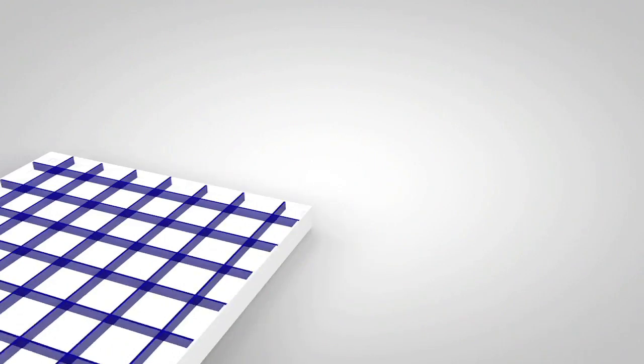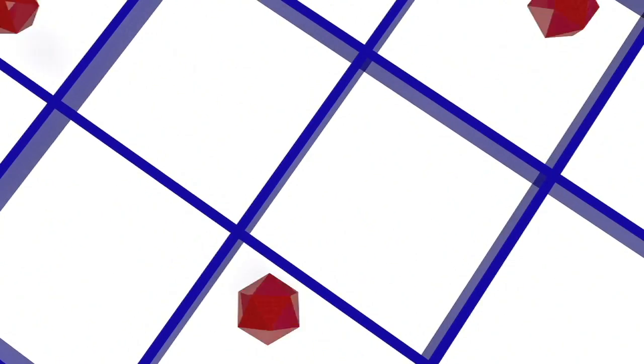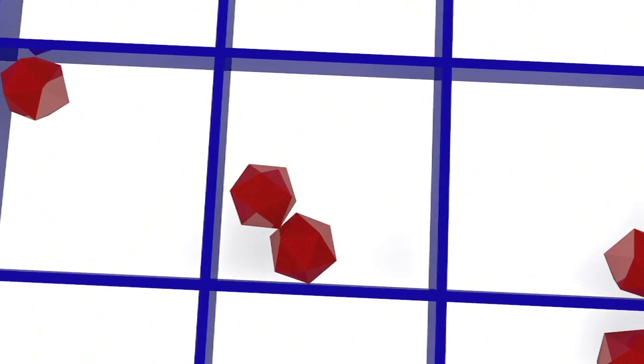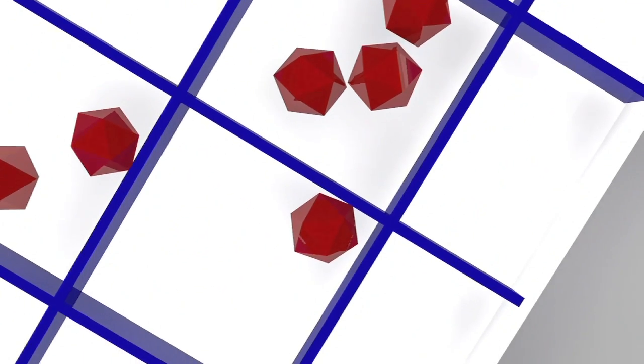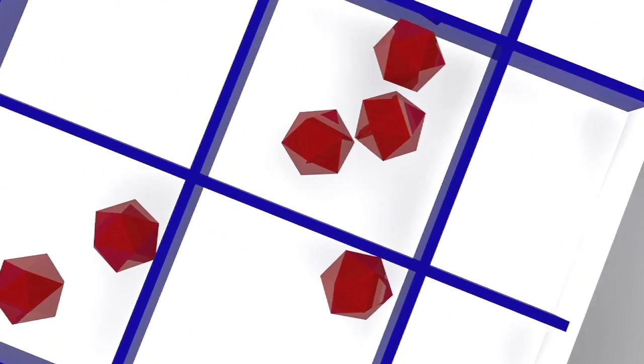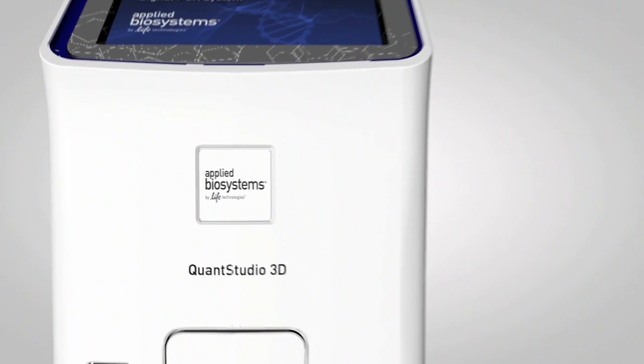To understand the absolute count, it is necessary to understand that some reaction wells will receive more than one target molecule during partitioning. Uncorrected, this can lead to undercounting, as only positive reactions are counted. This mathematical issue may seem daunting, but fortunately a digital PCR instrument, such as the QuantStudio 3D from Life Technologies, figures this out automatically with the use of standard statistics.